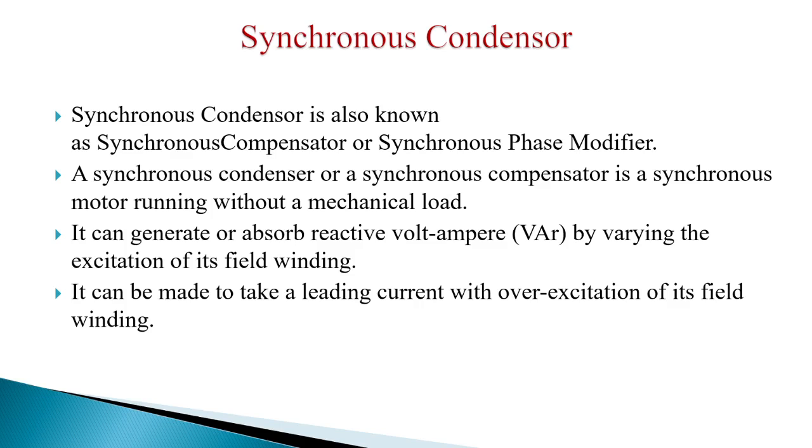A synchronous condenser or synchronous compensator is a synchronous motor running without a mechanical load. So we are not giving any mechanical load to this motor, and we are running it. It can generate or absorb reactive volt amperes by varying the excitation of its field winding. Okay, so the field winding will be there, and we are varying its excitation, and it will generate or absorb the power.